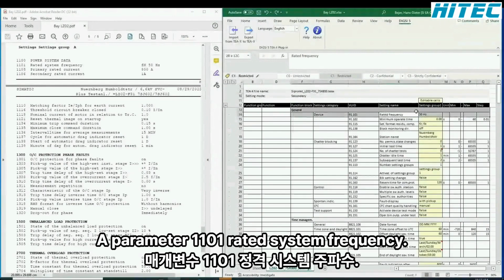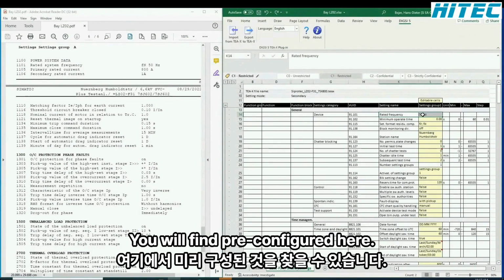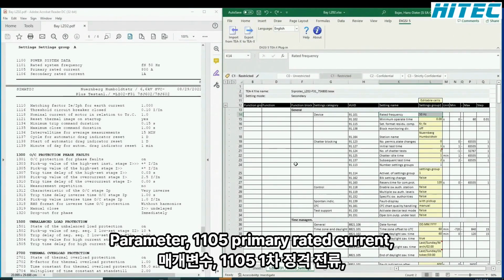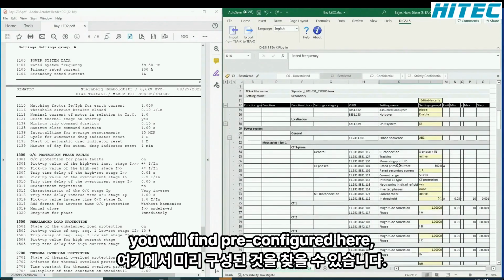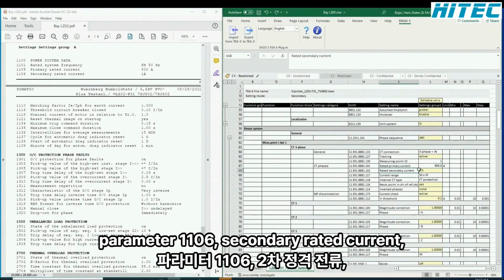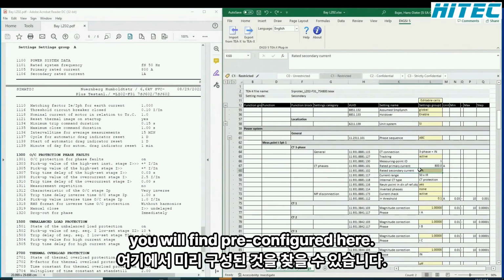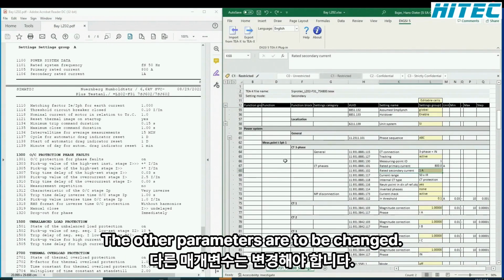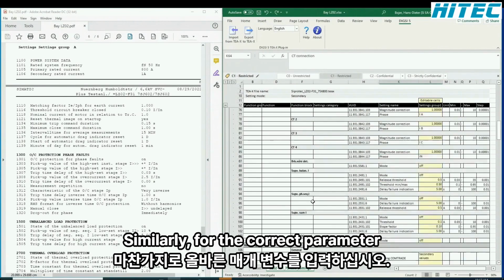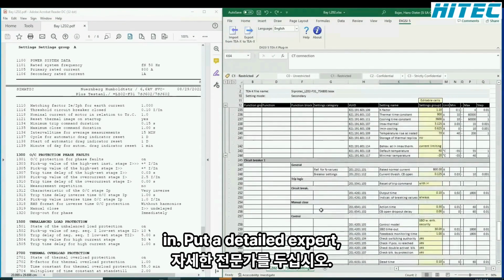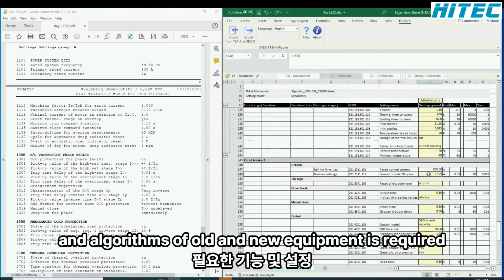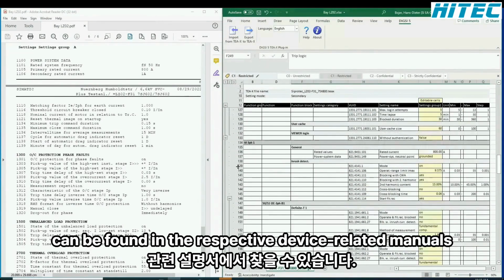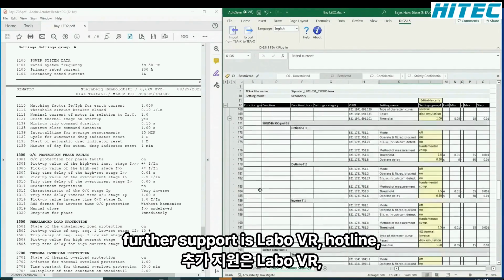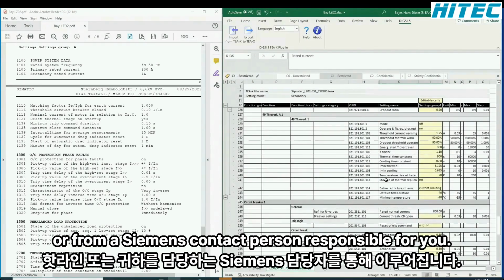Parameter 1101 rated system frequency you will find preconfigured here. Parameter 1105 primary rated current you will find preconfigured here. Parameter 1106 secondary rated current you will find preconfigured here. The other parameters are to be changed similarly. For the correct parameter input, detailed expert knowledge of functions and algorithms of old and new equipment is required. Functions and setting instructions can be found in the respective device-related manuals. Further support is available via our hotline or from a Siemens contact person responsible for you.